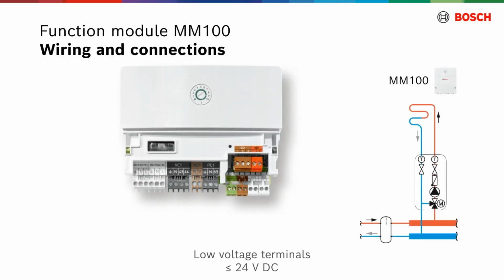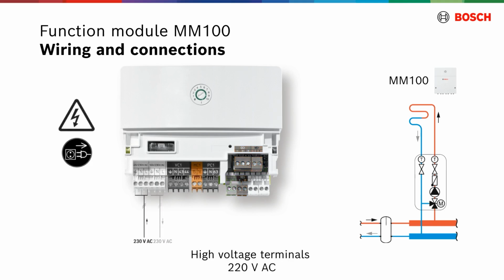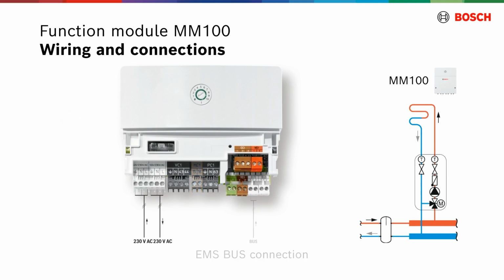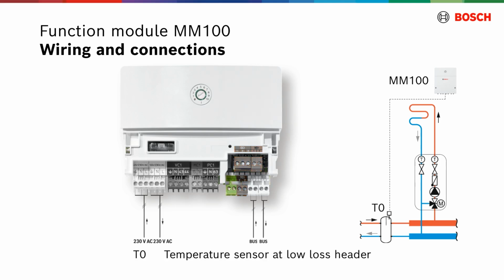It has low voltage terminals for the temperature sensors and the safety limiters, and high voltage terminals for the power supply, pumps and valves. On the low voltage side, there are terminals for the EMS bus connection. The module records the temperature at a low loss header with the temperature sensor T0. This should be connected to the function module MM100 with the coding switch position 1.